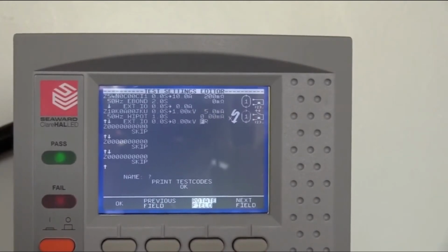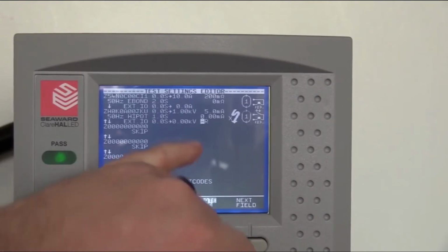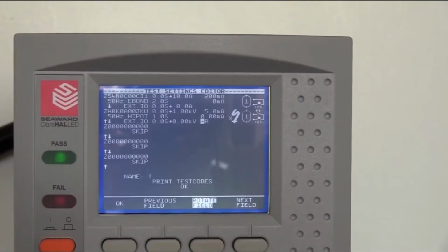And the next thing, for those of you that have a 103 or a 104 or are considering a 103 or 104, we can choose where to send the test voltage. So we can send it via the front ports, which we saw earlier with the 2 white ports at the front of the unit, or to the rear port, which is the output box that we showed you as part of the unboxing. Now, for this particular test, we're going to be testing a product that has a plug, so it's convenient for us to use the socket on the output box. So we're simply going to turn off the front port, meaning we're now only testing to the rear port.